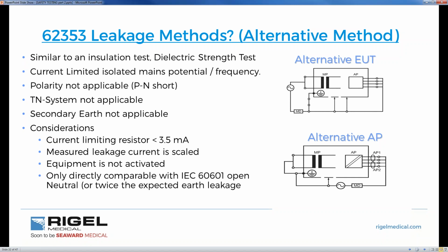The alternative method is similar to a DC insulation test, but we're using AC. So we're simulating dielectric strength tests, but using only mains voltage. We short live and neutral together on the input of the conductors that power the device, and then we apply an isolated voltage at mains potential between all of these connections coming together and the protective earth. This is our enclosure or chassis, any conductive parts, and our applied parts. So we don't power the medical device. It doesn't get powered at any time. We're just testing between the conductives, with live and neutral shorted, to our important return points to try and measure any leakage via our 1K body model measuring device.